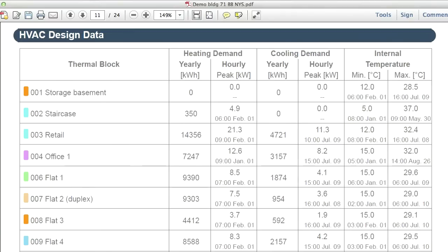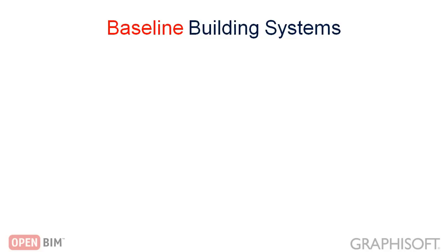The minimum and maximum internal temperatures are also displayed in the HVAC design data chapter for each thermal block. This is important information because it shows whether the energy model is valid throughout the entire reference year for every thermal block, or there are times when the internal temperatures do not meet the thermal comfort requirements. The hourly peak heating and cooling load data is the most important information required to determine the appropriate size of the necessary building systems for each thermal block.